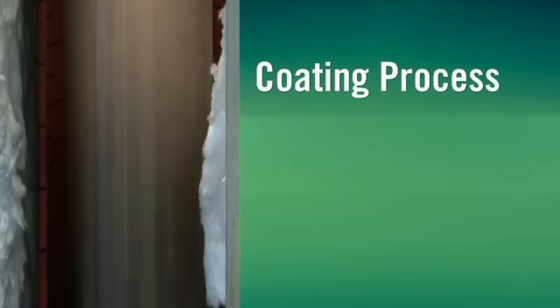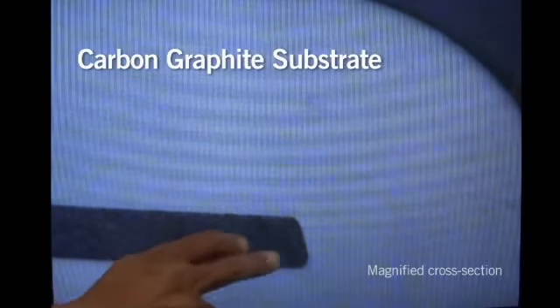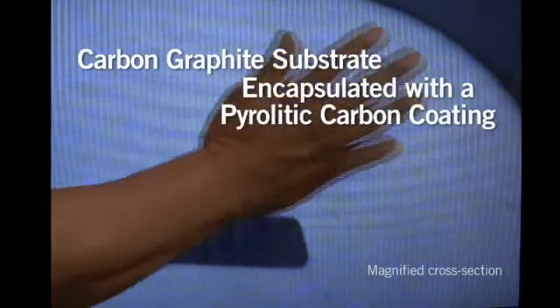The mechanical valve components then proceed to a highly specialized proprietary St. Jude Medical carbon coating operation. This chemical vapor deposition process provides essential strength and wear durability for the valve components utilizing a fluidized bed. The result is a carbon graphite substrate component entirely encapsulated with a pyrolytic carbon coating. This specialized process is unique to St. Jude Medical products.